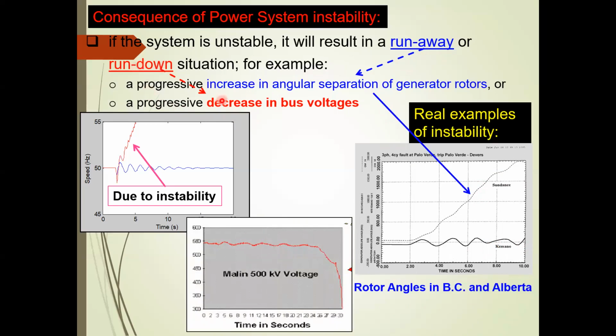if you refer to the rundown situation this way, what you find here is that the bus voltage is about 550 kV, right? The steady state value at 0 time is 550 kV here. We find that there is some disturbance taking place, and there is some deviation in the bus voltage here, right?